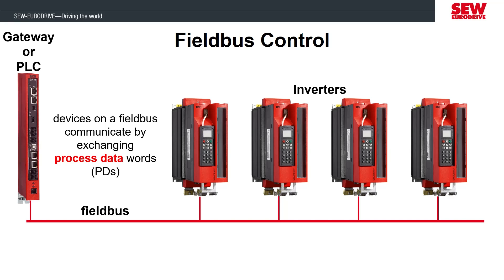Three words is not a limitation. It is possible to do more or less process data words depending on how the Movi Drive is configured and the limitations of the hardware. Also, if there are multiple VFDs, each one doesn't have to receive the same commands. It is possible to send unique commands to each one at the same time, so there is flexibility there too.